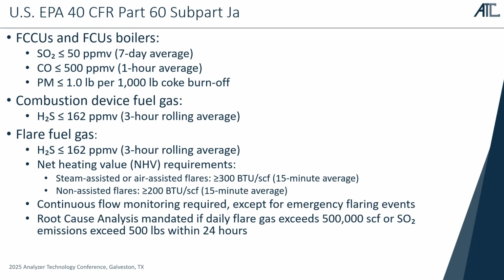You can see here some of the limits that are mandated. There are different ppm values and different averages they need to calculate, as well as totals of the emissions. And they also mandate H2S, hydrogen sulfide limits for combustion device fuel gas, so things that go into boilers and heaters and appliances, as well as for the flare fuel gas.